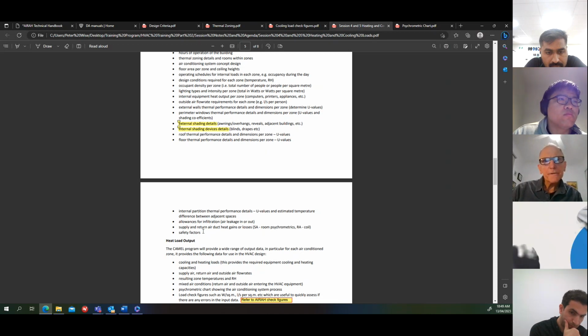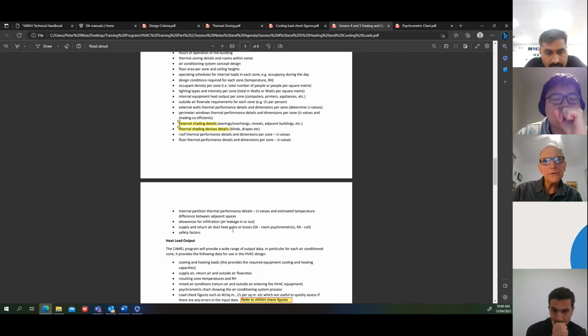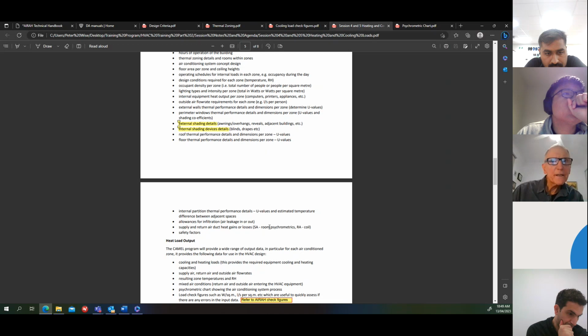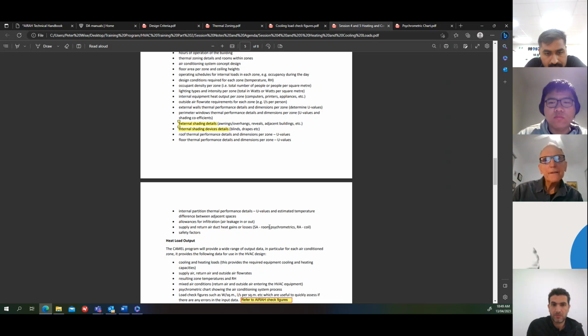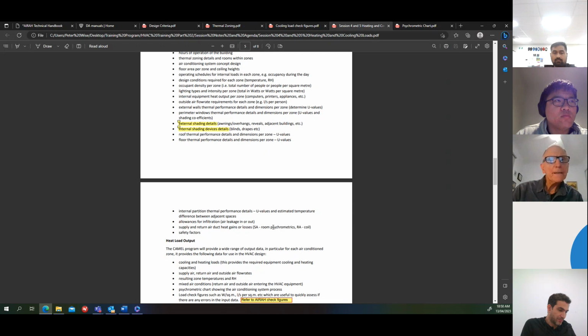Now, Camel will also ask you for a few extra things like supply and return air duct heat gains or losses. If it's a supply air duct gain, if you've got a long run of supply air duct and it's in a hot space, say the ceiling is hot, it's got a roof over it, depending on the insulation, there may be some heat gain to the supply air being delivered to the room.